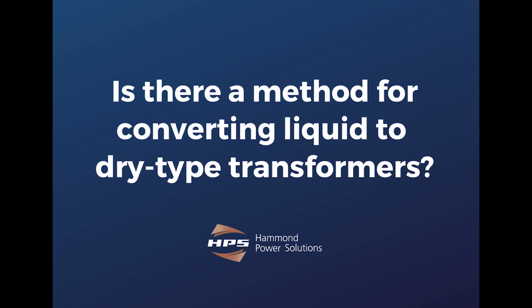But again, one of the things we're trying to get across from this presentation is that if you do have a liquid filled specification, it is very ineffective. In fact, in most cases, we'll probably just reject it to give a dry type equivalent. What we really need is for the end customers to say, hey, I would like to consider a dry type, and here is an actual dry type specification in order for us to do it. Because there are so many site considerations in the evaluation, it's not something manufacturers such as us are best equipped to do. That really is something the specifying engineer or end users would have to do.